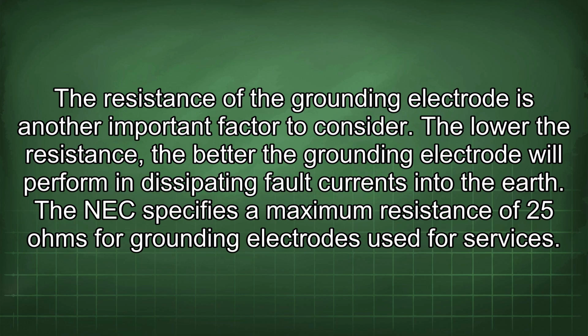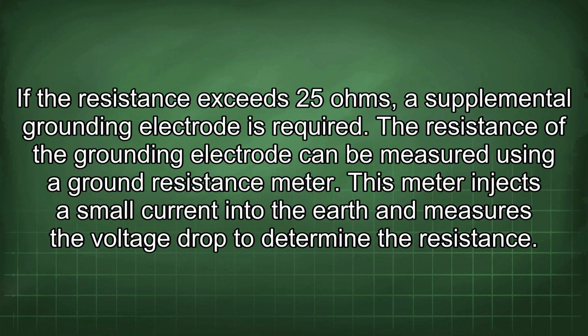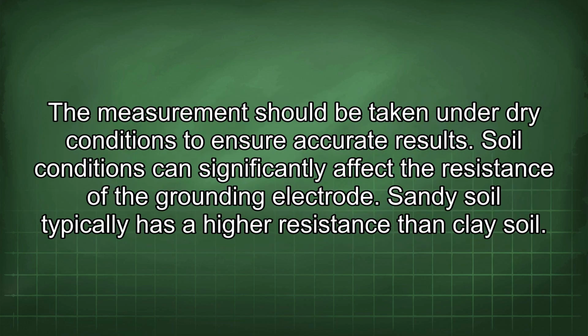The resistance of the grounding electrode is another important factor to consider. The lower the resistance, the better the grounding electrode will perform in dissipating fault currents into the earth. The NEC specifies a maximum resistance of 25 ohms for grounding electrodes used for services. If the resistance exceeds 25 ohms, a supplemental grounding electrode is required. The resistance of the grounding electrode can be measured using a ground resistance meter. This meter injects a small current into the earth and measures the voltage drop to determine the resistance. The measurement should be taken under dry conditions to ensure accurate results.